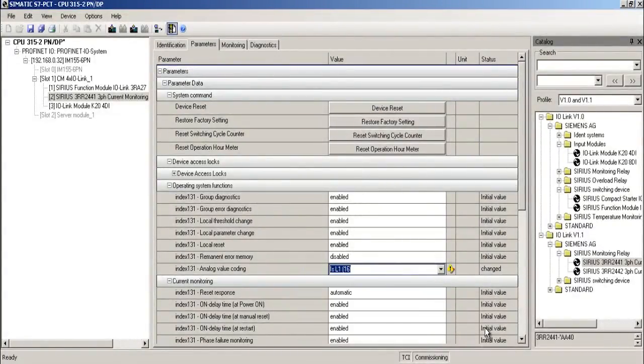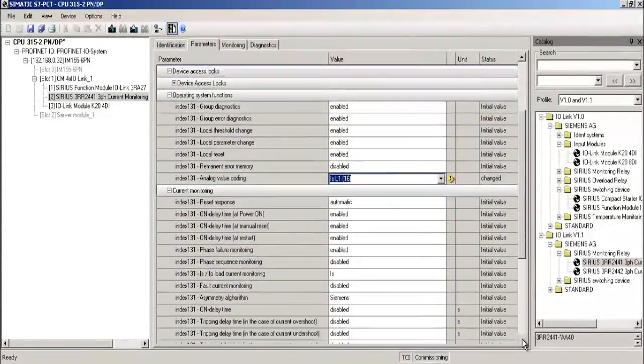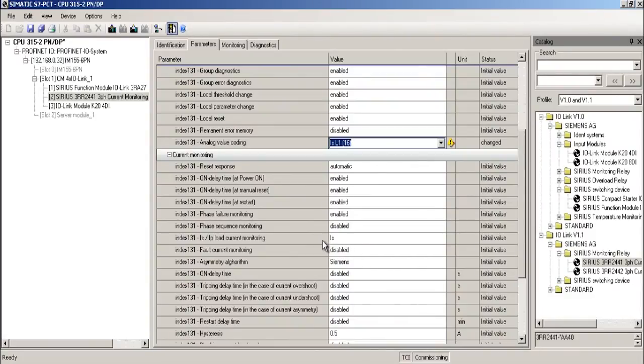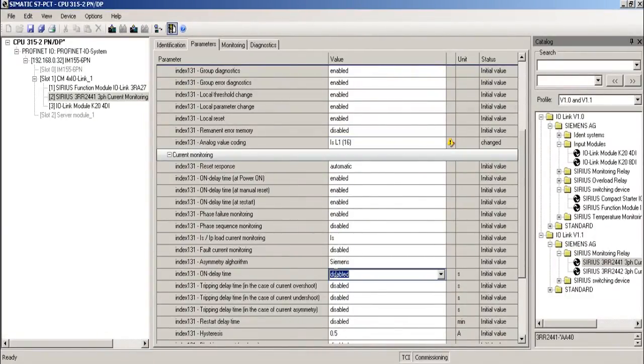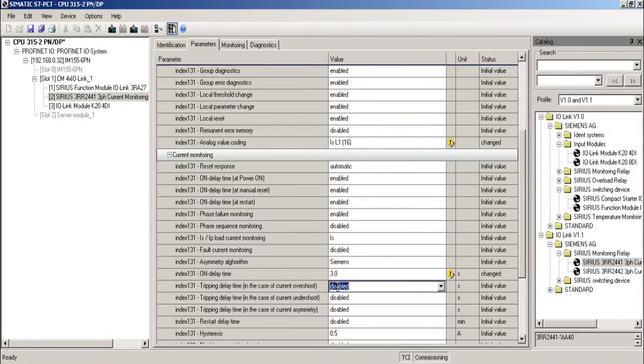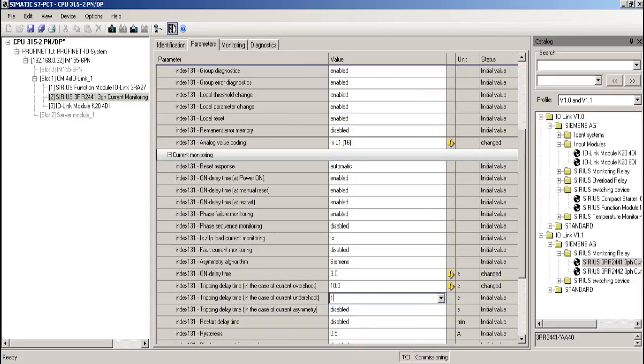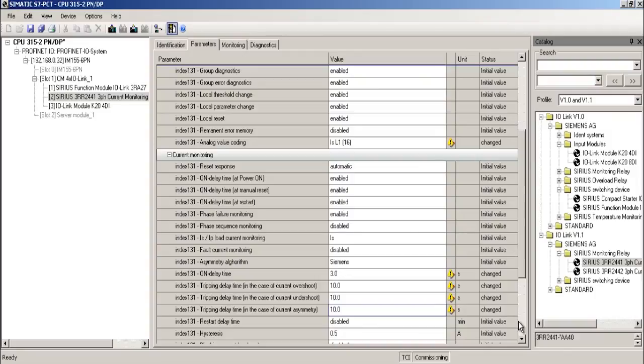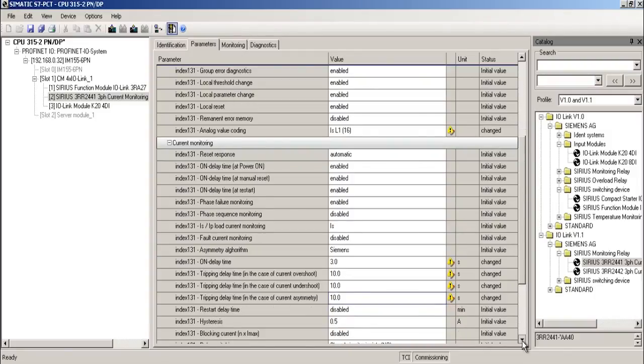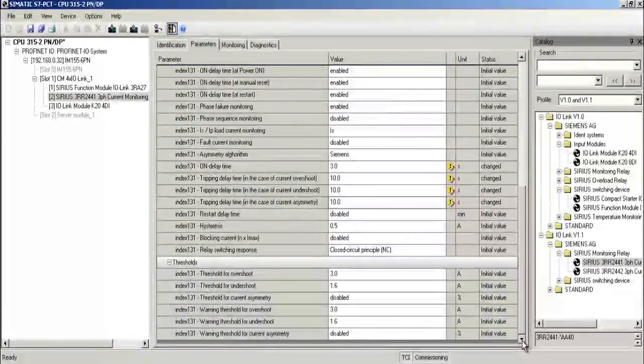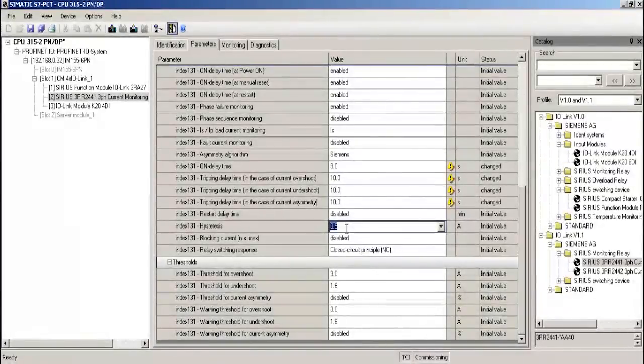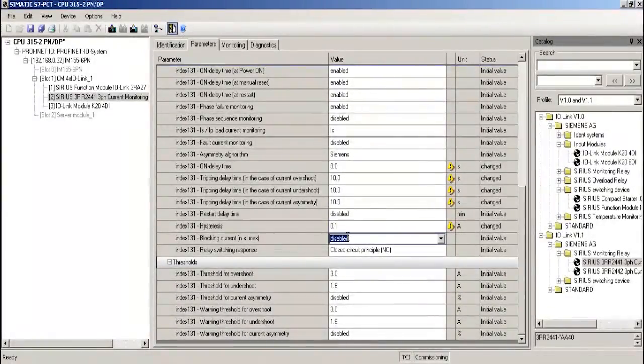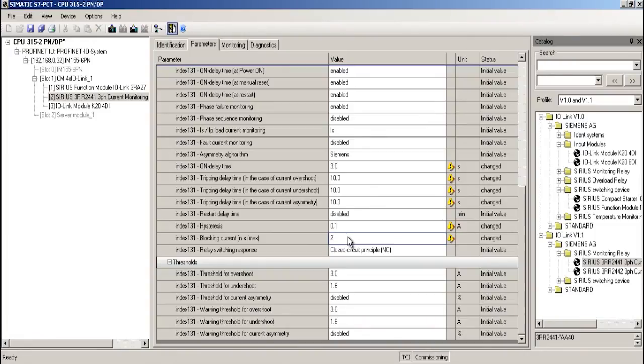For the following current monitoring functions, I leave load current monitoring as apparent current. I set the starting delay to 3 seconds. I set the tripping delay times to 10 seconds. These are the delay times until the screw changes the direction of rotation based on overcurrent or undercurrent and triggers a fault. I select 0.1 amperes for the hysteresis and double load current for the blocking current.